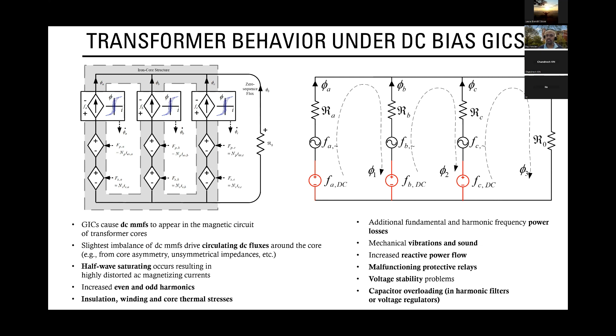Here is what those currents look like. This was done in my lab on a set of transformers. Let's look at the left here. You can see a range of GIC that we artificially injected. I have three windings in that transformer, and the current is supposed to be centered around the zero axis. But when you have increasing GICs, as you get into the red region, that waveform gets shifted up. The alternating current gets shifted up and gets peaky. You get these very large, sharp peaks, large enough to cause overheating and damage to the windings of the transformer. And it also happens in the reverse direction, the negative peaks.